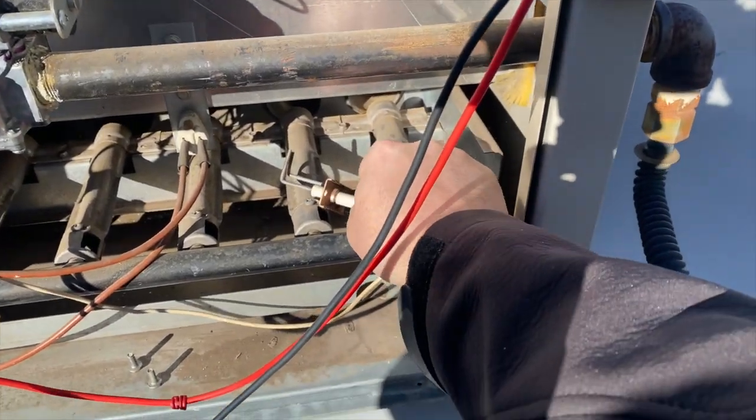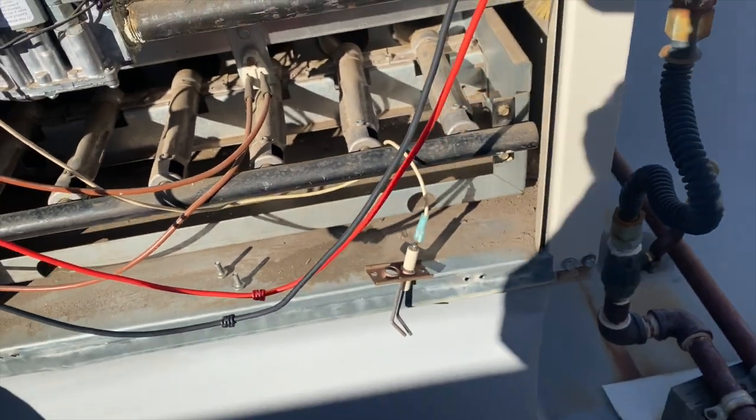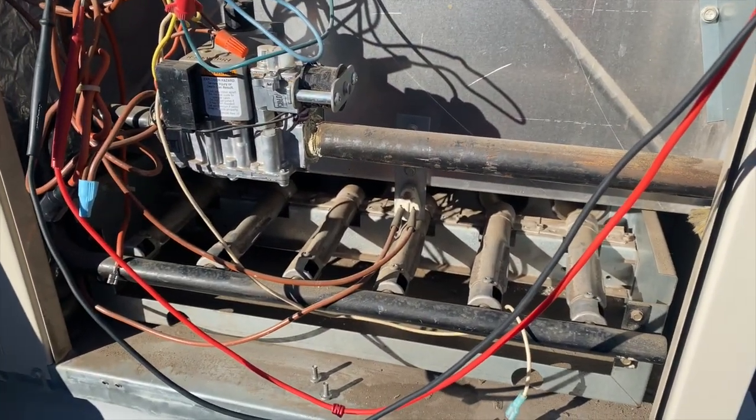We got our igniter, it's not super dirty, I'm going to clean it. Here's a weird thing, here's our flame sensor, it looks like it's actually an ignition spark ignition assembly but I guess it technically works the same thing, this lower voltage, so I'm going to clean that too. That's actually kind of weird, I wonder if that's supposed to be like that. There's a bunch of other units exactly the same, I'm going to check those out. We're going to go ahead and get this cleaned, put it all back together, make sure all the connections are tight and then we'll try to fire it up again. If not, I'm thinking it's just the ignition control module might be bad.